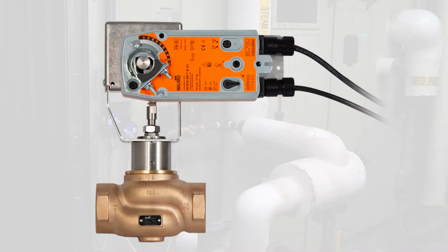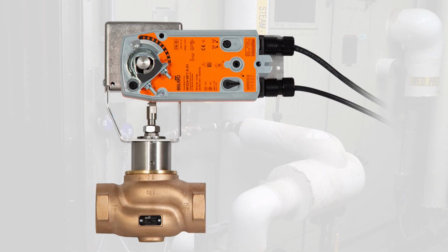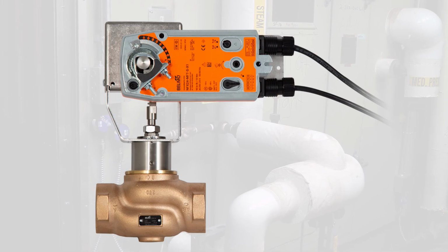How it's different is if it's under pressure, and when I say from a boiler, I'm thinking of PSIs, because the boiler's operating at, let's say, 5 PSI or even higher. You can use smaller piping. It's under pressure to get it from one spot to another. And from a boiler standpoint, now you need to control how much there is. So you're going to have a valve regulating how much moisture goes into the dispersion panel. Versus you can regulate heaters or a gas burner to do that same thing if you don't have the boiler already.